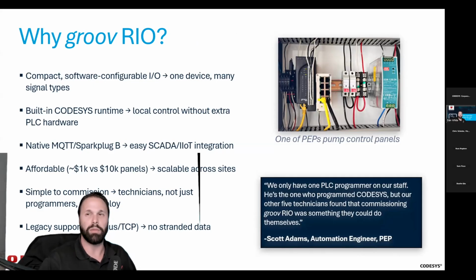First, it's incredibly flexible I/O. With 10 points, each channel software configurable, the same device, the same part number, can handle digital, analog, thermocouples, pulse inputs, counters, you name it. So with one piece of hardware they could handle their radar sensors, their pump contactors, their turbine flow meters, all with just one device, without choosing separate I/O modules.